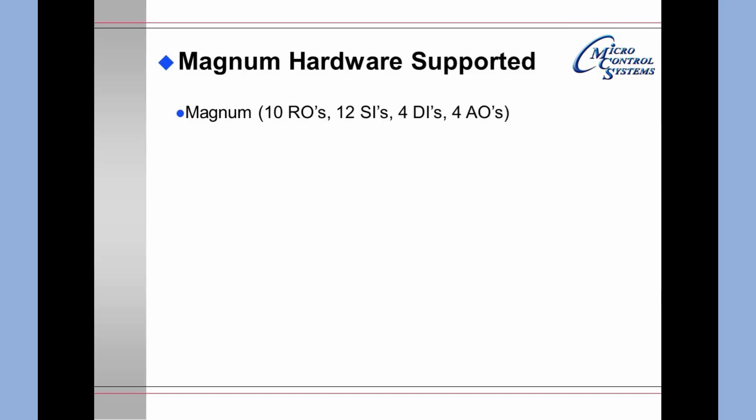The Magnum hardware will support 10 relay outputs, 12 sensor inputs, 4 digital inputs, and 4 analog outputs on the main processor board. The MCS IO board is capable of supporting 8 relay outputs, 8 sensor inputs, and 1 analog output.